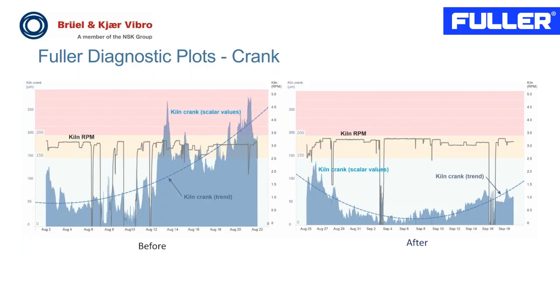So if we have a case where, due to the fuel mix and the use of alternative fuels, we cannot completely avoid a crank, then what we do is monitor the accumulated damage, and then we can recommend the customer to do preventive measures such as NDT testing in order to check if there are any cracks present in the equipment, or to see if any of the cracks are propagating. So that is the preventive measures in case the crank cannot be avoided.